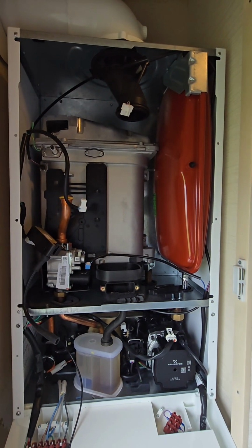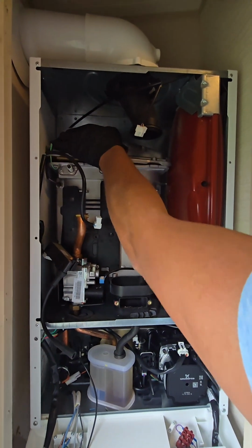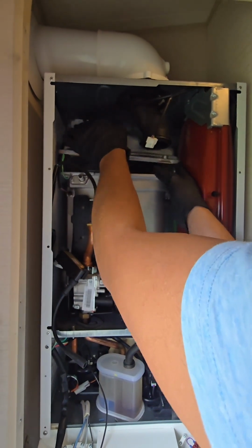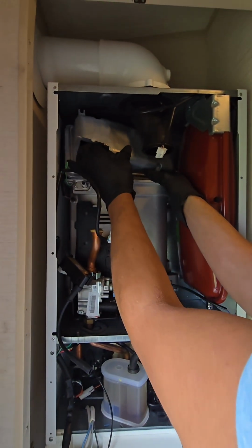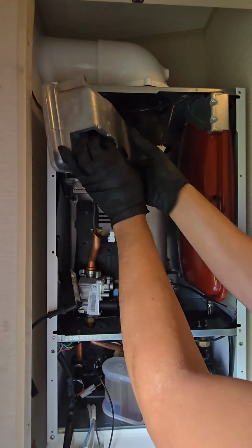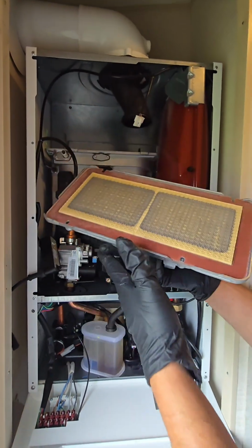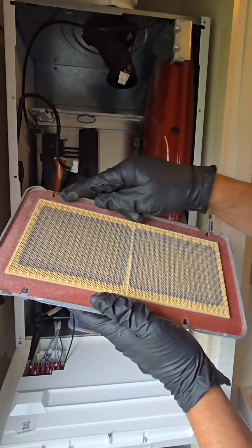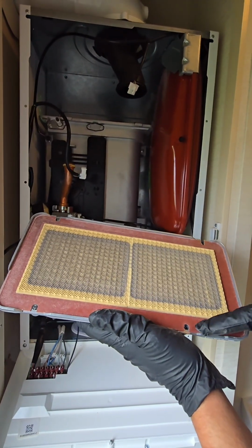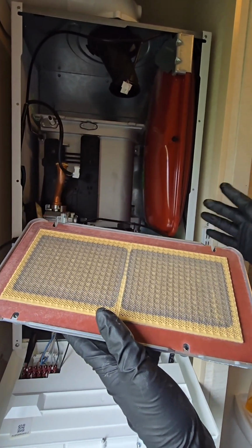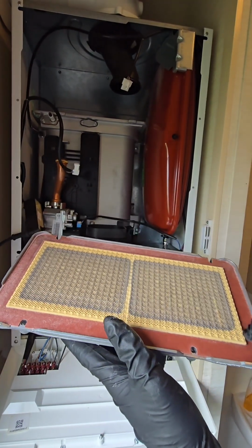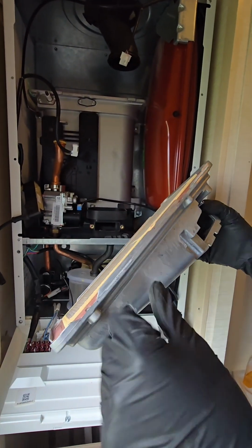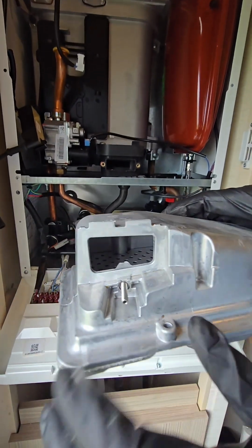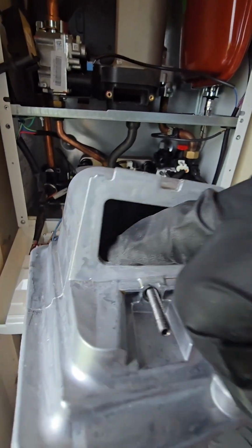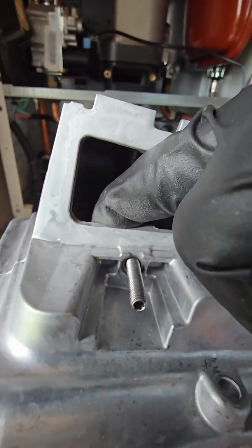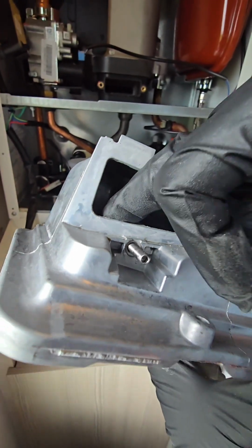Right, so the bolts securing the burner have now been removed. So if we lift up the burner, tilt it towards you and turn it to the side, the burner will then come out. We fully inspect the gasket seal. This one is fine. You normally find on Ideal and MORCO appliances that these are very rarely deteriorated, to be honest. Then if you turn it over and check the burner plate. Now there should be a little bit of movement in this, but not excessive. Again, this one is absolutely fine.